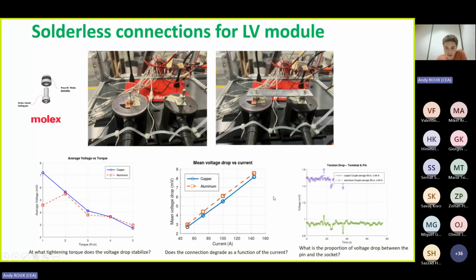We also had another question: does the increase of current affect the voltage drop? What we can see here is a straight, linear line, meaning the resistivity is constant. That's good, because what we don't want to see is that when the temperature rises too much, the resistivity increases, indicating degradation around the connection.